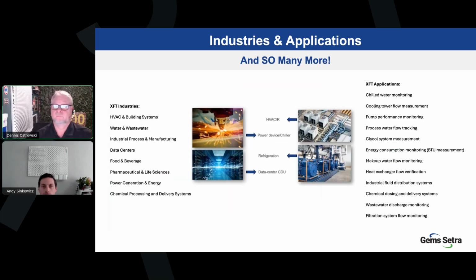Okay, next. But that's not all, right? I just covered a few of them that are live in the field right now, but we do have others. You see HVAC, water and wastewater comes to mind. Industrial process and manufacturing, data centers. Data centers I want to highlight here because a data center, no leaks, right? Leaks are a bad word. So no leaks, no pressure drops. They perform well in primary and secondary loops and in coolant distribution units. So we've already had some interest from some CDU manufacturers because of its no contact and no chance for leaks. So that is definitely a good selling point for this product in that industry.